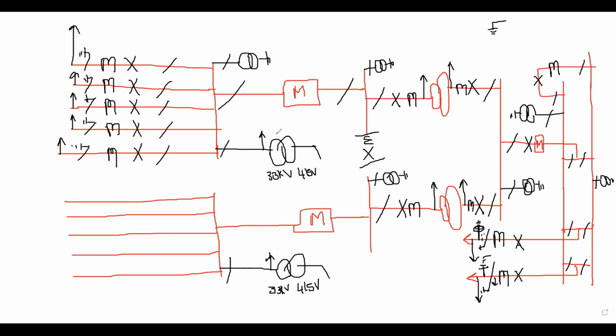Now, in a 33 by 220 kV substation, the auxiliary consumption load is mostly 250 kilowatt maximum, or less. So for a 250 kVA transformer, what would be the current at 33 kV? Just calculate what the current would be at 33 kV. Let me show you.